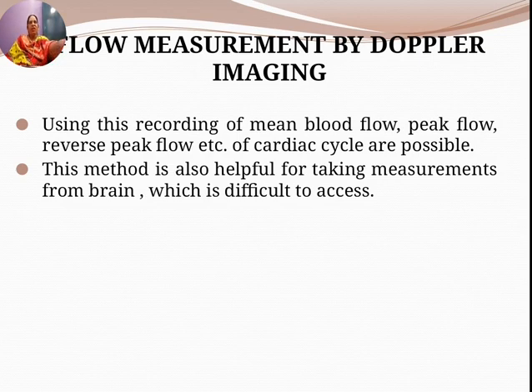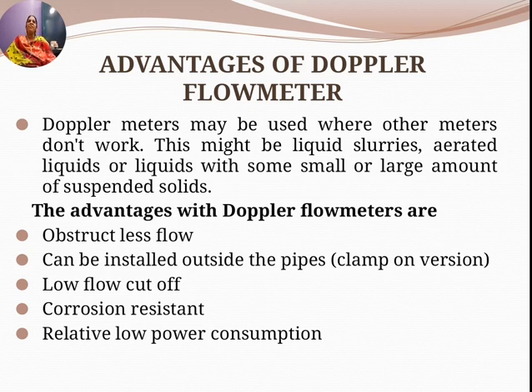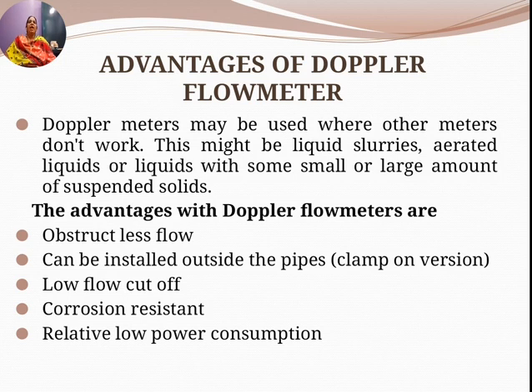Advantages of Doppler flow meters: they may be used where other meters don't work, such as with liquid slurries, aerated liquids, or liquids with suspended solids. They obstruct flow very little, can be installed outside the pipes, have low flow cutoff, are corrosion resistant, and have relatively low power consumption.